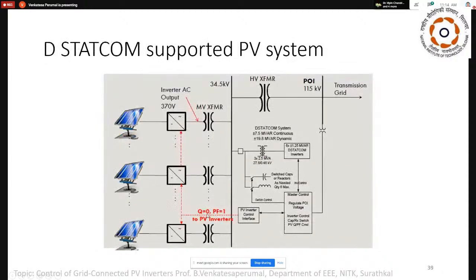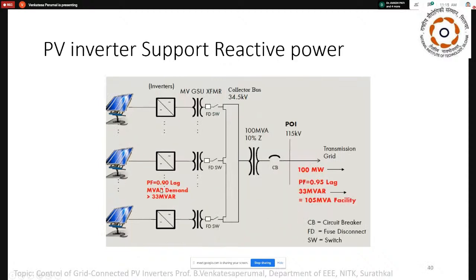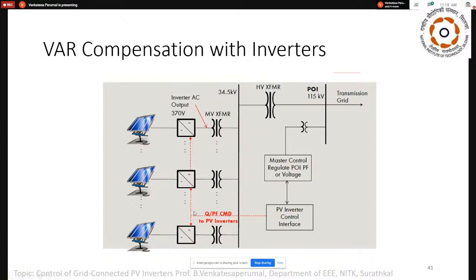I'm coming to the point where Q is 0, power factor is 1, all the inverters are working, and to get transmission line stability, VAR compensation, these STATCOMs were used initially. In the initial days they were using STATCOM, which has been replaced by each inverter supporting 0.9, so the entire system complexity is going to come down. So you can see that the lagging and leading can be supported from the inverter itself.